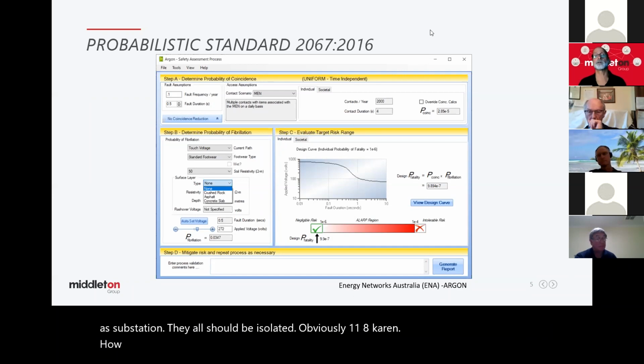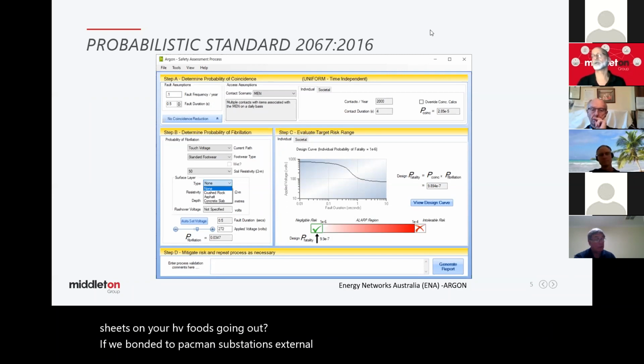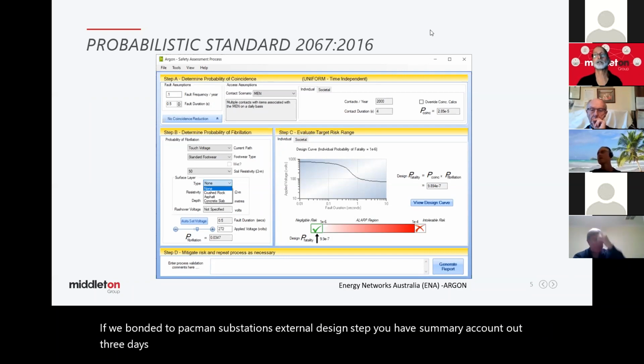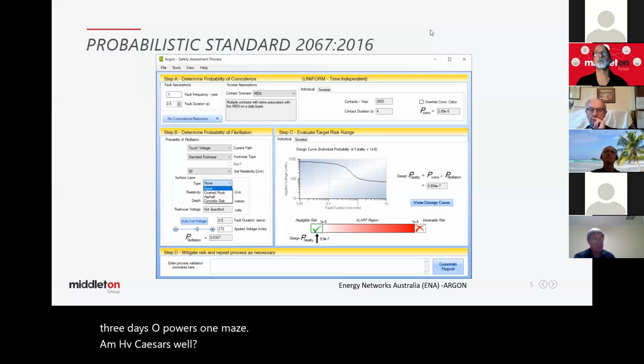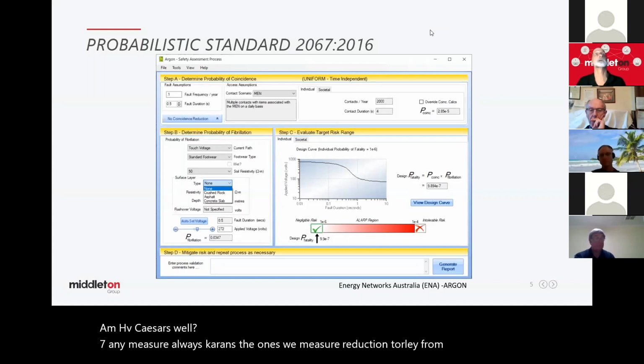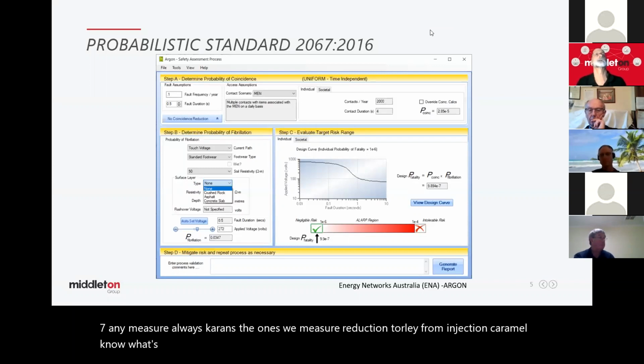Auxiliary paths also going out of the substation quite often are underground cables. The cable sheaths on your HV feeders going out, if they're bonded to pad mount substations external to the zone substation, you'll have some of your current go out through those auxiliary paths along those HV feeders as well. So we need to measure all these currents. The ones we measure, we deduct vectorially from our injection current, and now we know what's going into the actual grid.